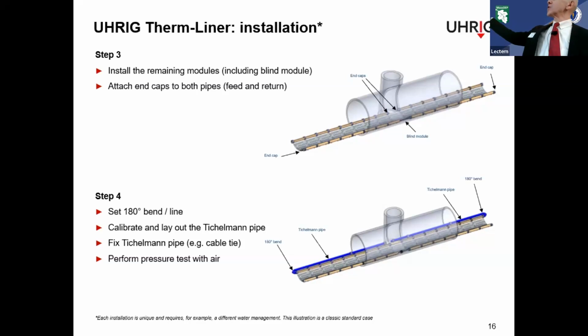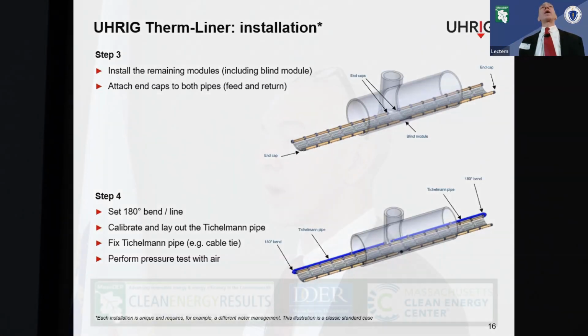And the heat exchangers are designed in size based on the need of the plant that you're trying to build, right? So if you're building a small system, it's a shorter heat exchanger with lesser sections. If it's a larger system that requires more energy, it's a larger heat exchanger that spans more of the base of the sewer, right?